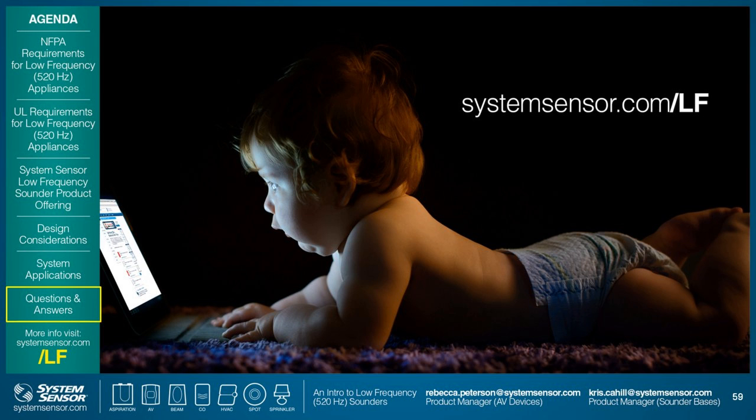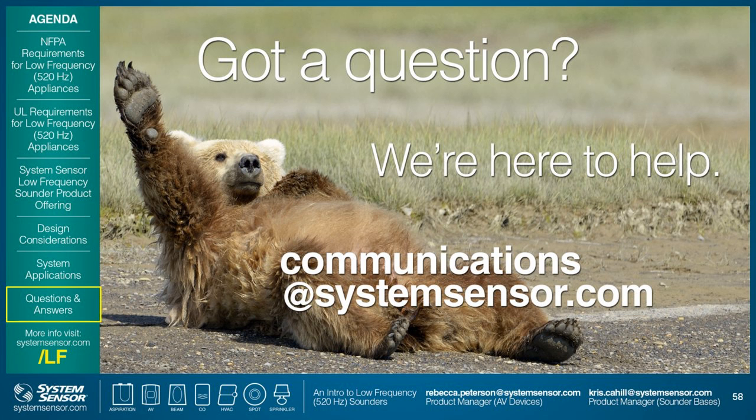That piezo element, you can really boost that up, and most of those devices, I'm not going to speak for every manufacturer, are hopping around a number of higher frequencies, anywhere between 2 kilohertz and 4 kilohertz. So you can really get a lot of sound output. Because you're focusing your energy so much on this lower frequency scale, the audibility isn't quite as high. So don't be surprised if you see for a temporal 3 around 76, 77 dB. Okay, all right.